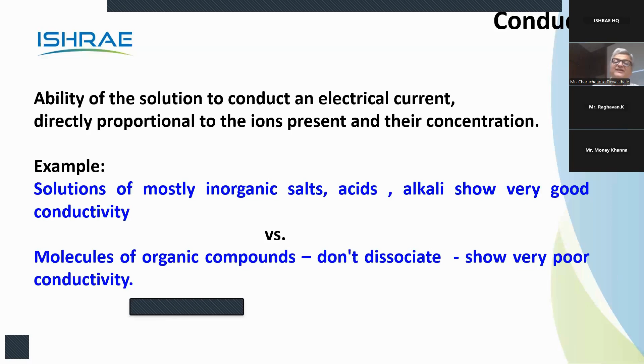So solutions of mostly inorganic salts, acids, alkalis show very good conductivity, whereas if I remove everything from water and make it H2O only, then it will not be conductive. Pure H2O is not very conductive. Molecules of organic compounds that don't dissociate will not show any conductivity. They will have very poor conductivity in the circuit. So conductivity is directly connected with total dissolved solids. So there is a connection we have established, that conductivity and TDS are interconnected.